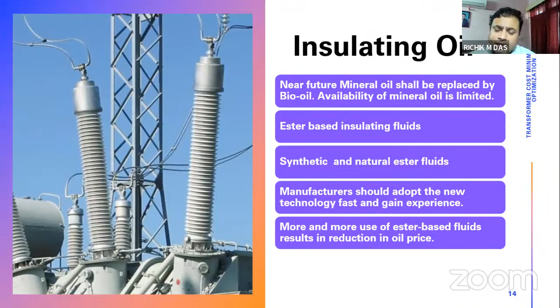This was about new material and how to handle it, because good storage is required for the oil. The oil serves insulation and cooling purposes. If we have good handling facilities, there will be less contamination, and parameters like tan delta, interfacial tension, and others will have good values.